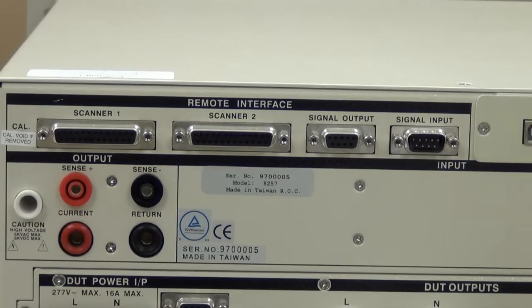The remote signal I/O output is a 9-pin D-sub miniature female connector which allows the tester to monitor pass, fail, and processing output relay signals. The remote signal input is a 9-pin D-sub miniature male connector for remote control of the test, reset, remote interlock disable, as well as memory selection bits. These relay signals are dry contact closures.